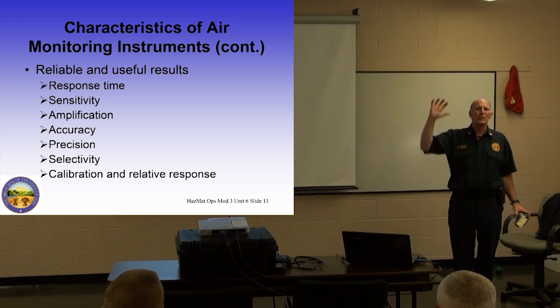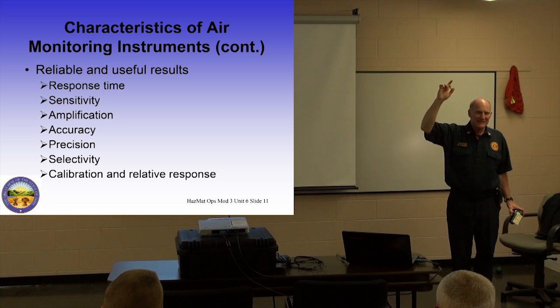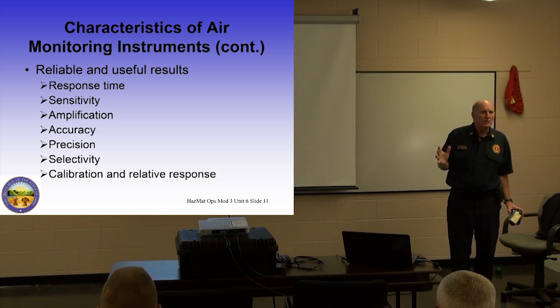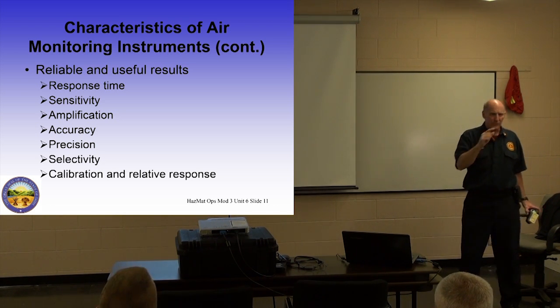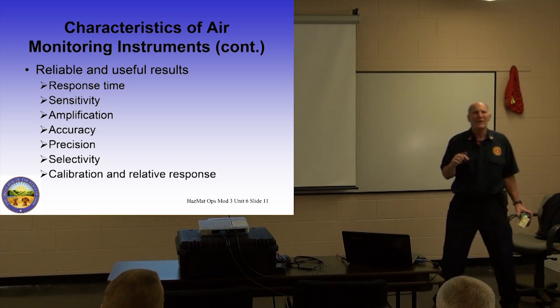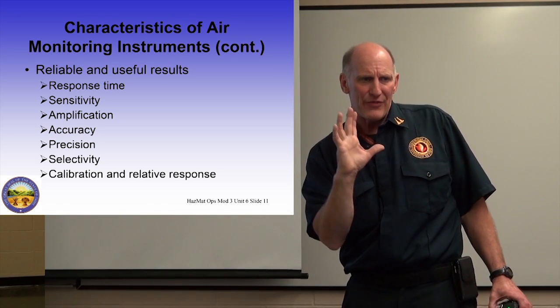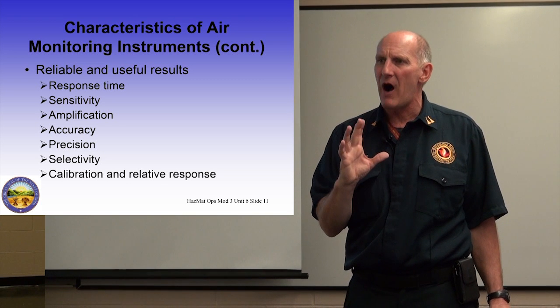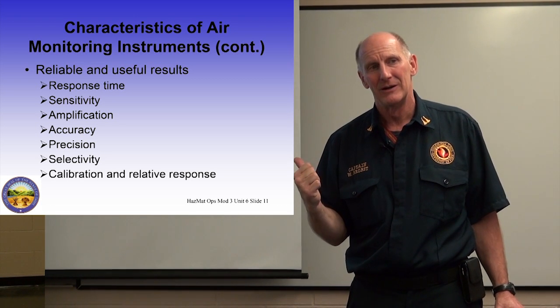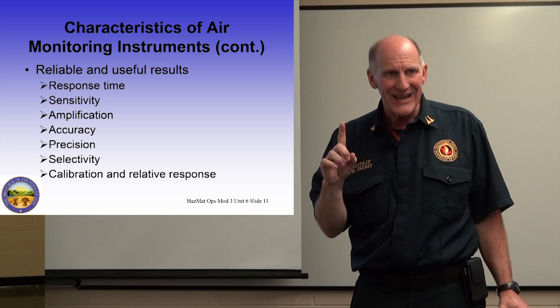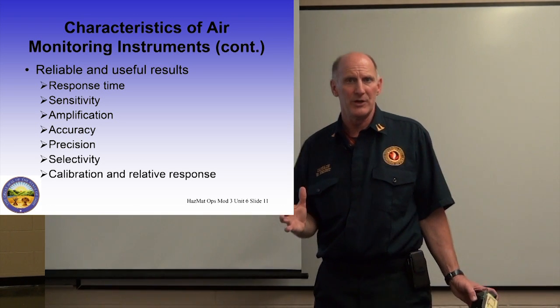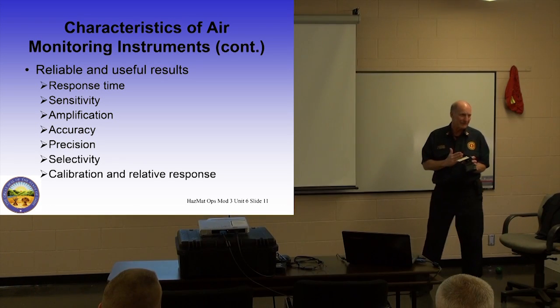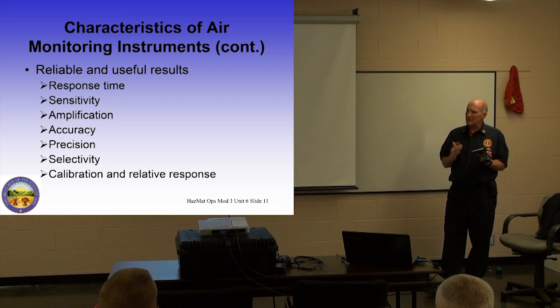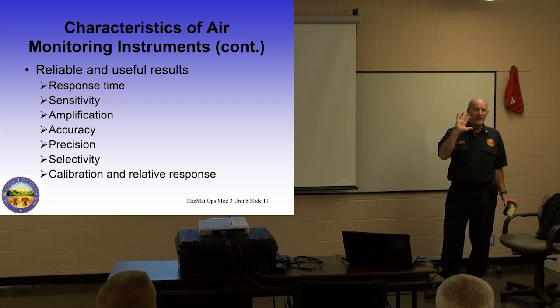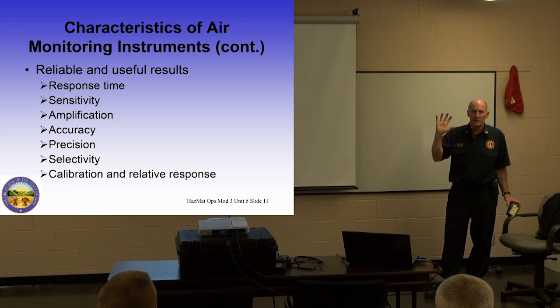It measures in percentages. And it's telling you it's 20.9 is normal oxygen. Well, the drop from 20.9 to 20.8 requires 1,000 parts per million of oxygen to disappear, because each 1% is 10,000 parts per million. It's not sensitive. The air monitor, as far as oxygen goes, will never drop if I put you in an atmosphere of 200 parts per million of some deadly chemical.